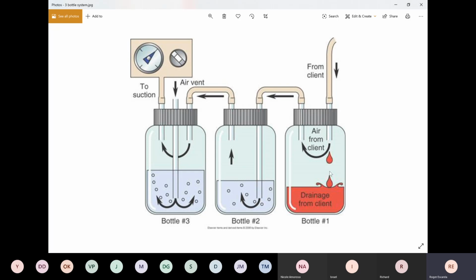And then if we're draining air now, air will always escape up. Air won't fall here. Air always goes up, so it'll escape here. As long as the drainage settles here. If this reaches higher, then you'll have to replace the bottle. So you need to get another bottle to replace this. Meanwhile, air escapes through this vent here, and then it will go into the second bottle.